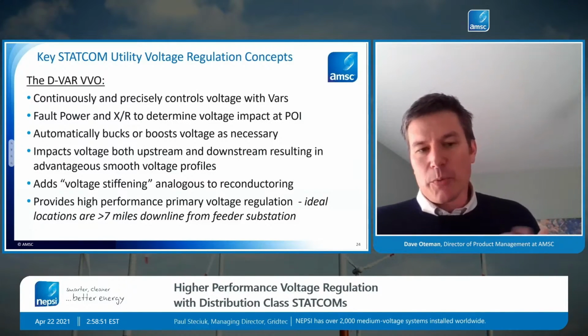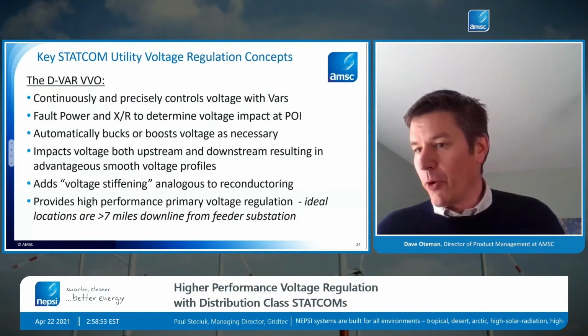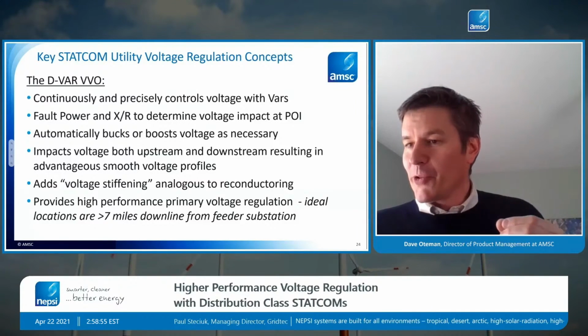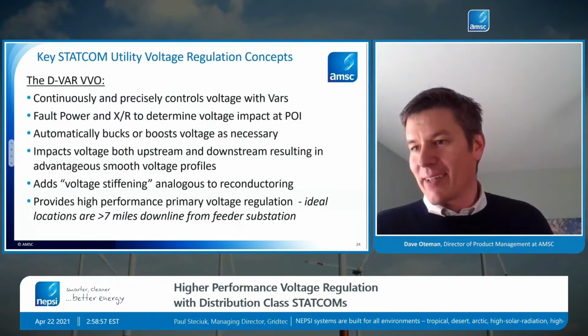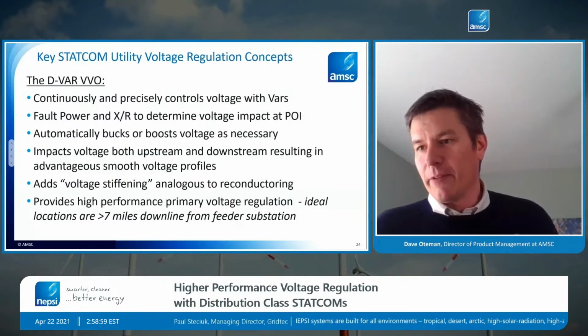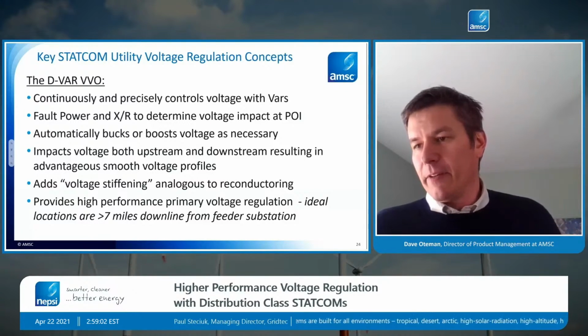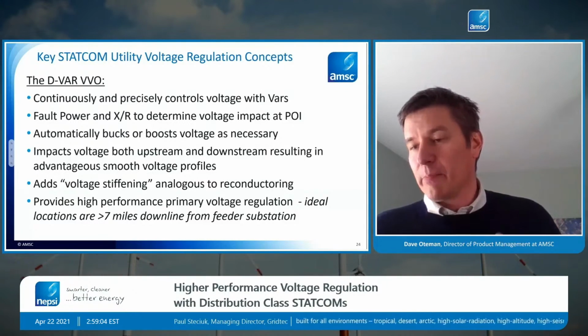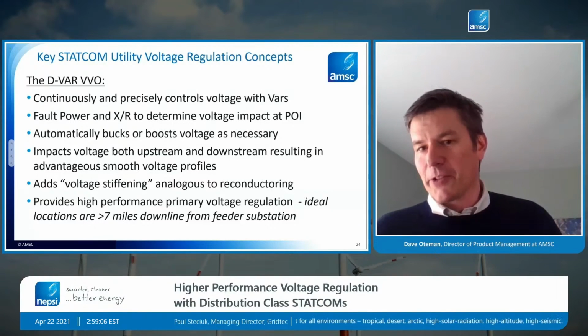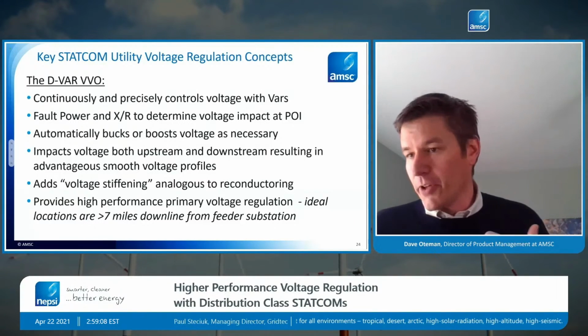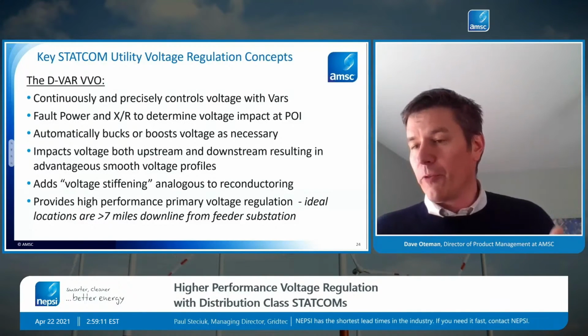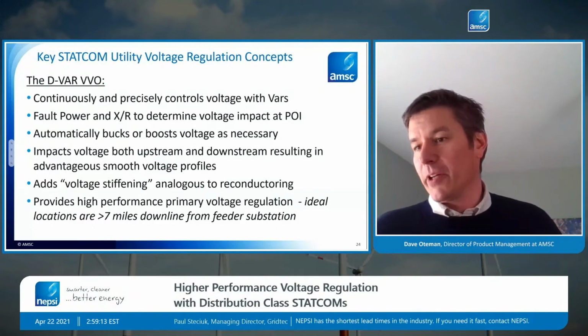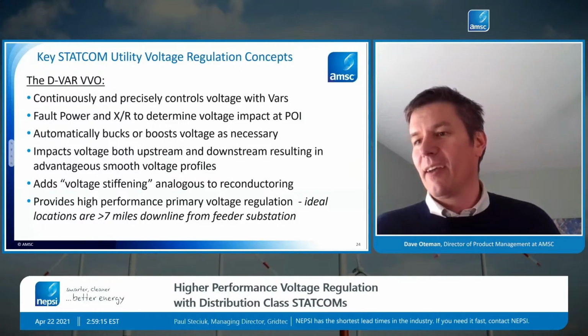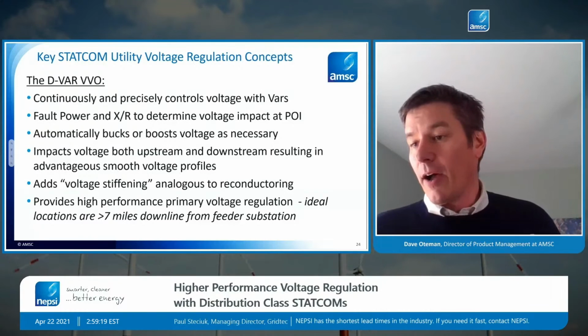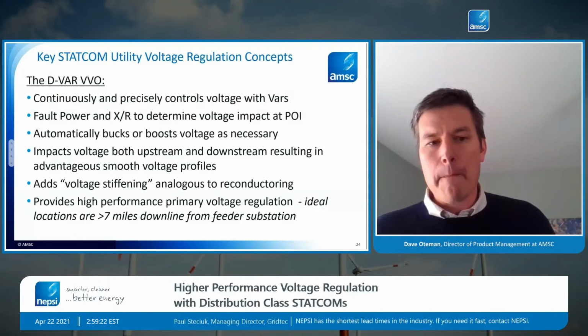And then, as we showed with those plots, this is a key point. As opposed to a series device, which only impacts voltage downstream of the point of interconnect, the VVO, being a shunt device, impacts both voltage upstream and downstream. And that results in those very nice smooth profiles. So we don't have the discontinuities that we get with series regulation, and we get nice flat voltage profiles, which are more efficient and have much better power quality.